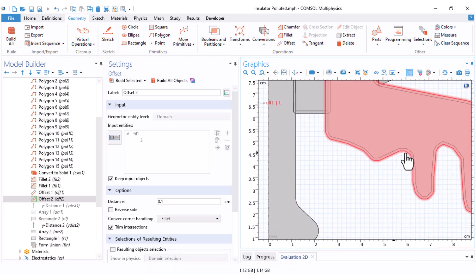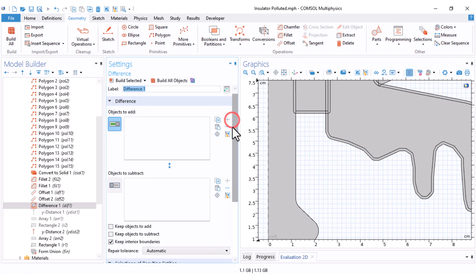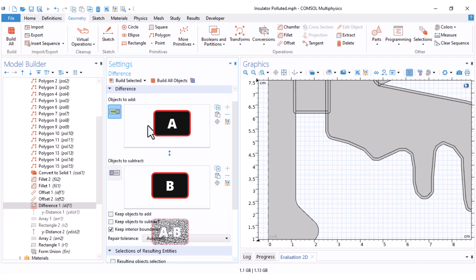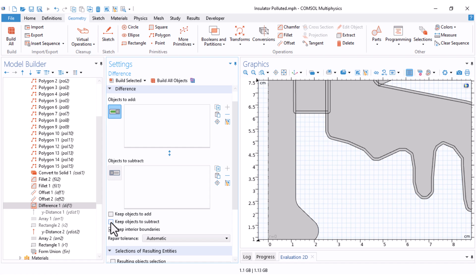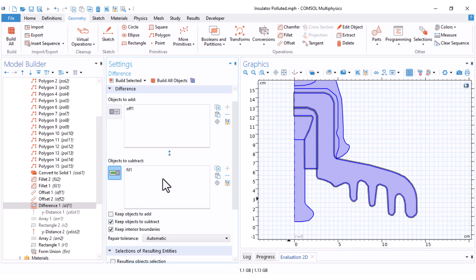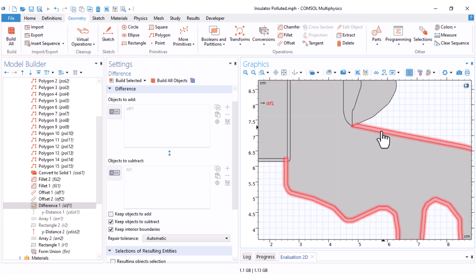To delete the extra parts and keep only the outer surface pollution boundary, there is a useful option under Boolean and Partitions called Difference. If I call the objects added here A and the objects added here B, when I click Build Selected the software performs A minus B. You can also choose to keep A, keep B, both, or remove both. I select the new offset object and the previous insulator unit overall, keep the insulator unit, and click Build Selected. The intersecting parts have been removed and we now have only a one-millimeter pollution layer over the surface of the insulator.